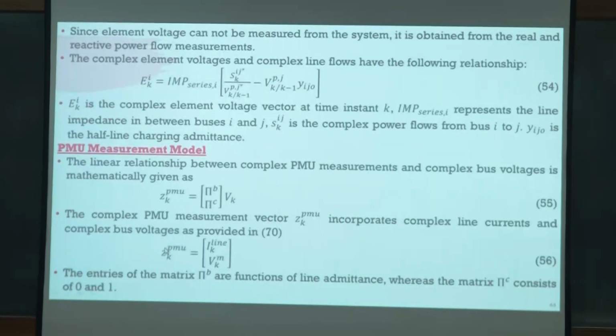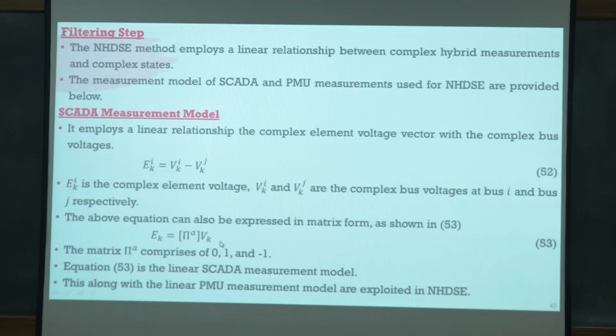Now, how to get this Ek? We get it from the active and reactive power flow of the system. This is a complex power flow, that is active power and reactive power, and the conjugate of that is taken and divided by the voltage, which gives you the current. This term stands for the current leaking through the half line charging. So this is the current flowing through the line impedance between the two buses. If we multiply that by the series impedance of the line, that gives you the voltage drop across the line. So that's how we calculate the element voltages, and equation 53 is our SCADA measurement model.